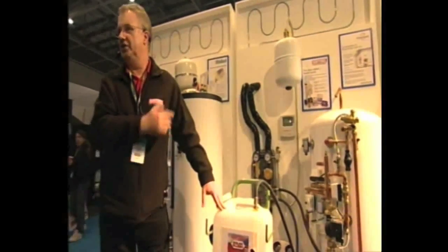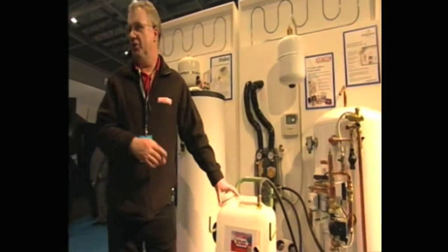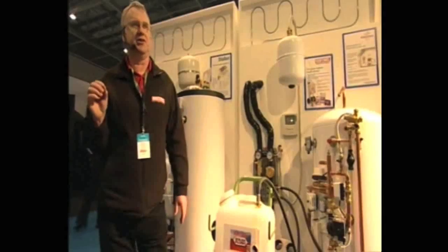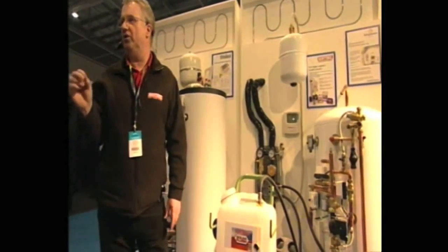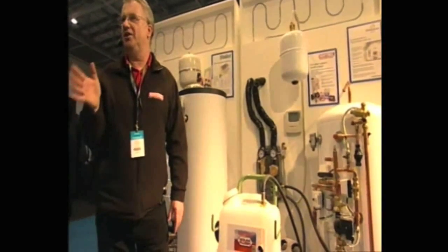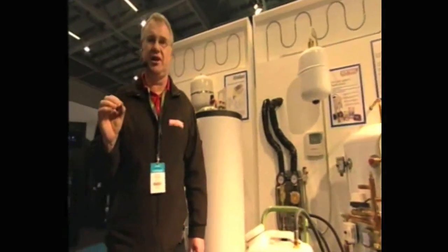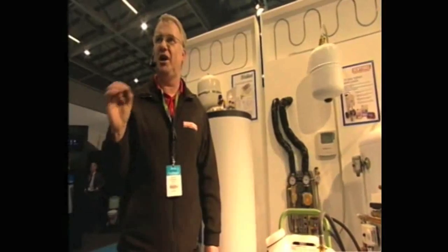You then drain the system into the pump, remove that degraded glycol. And then you must use a cleaner in the system that's going to remove all the degraded glycol from the system. This is absolutely critical for your customer. Because if you don't remove the degraded glycol and put more glycol back in, the new glycol will degrade quicker.